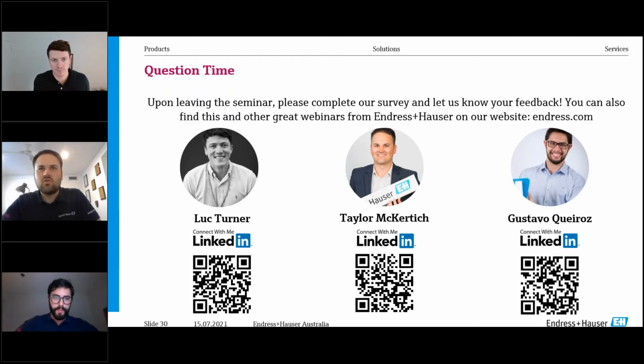Excellent, thank you. We've got about 45 seconds left, so I'll go with one last question. This one is about the Promag 400, so I might give this one to Luke. Yeah, I'll take this one. Richard's question is about whether there is still a limit on the maximum diameter for which OIML R49 approval is available. So Richard, at this stage, the approval is only available for the 400 series. We are limited up to 800 mm at this stage, but we are working with our factory in Europe to get that approval for the larger line sizes as well. So hopefully up to 2.4 meters at some point. But as you can imagine, it's a pretty long process, but we are working on it.